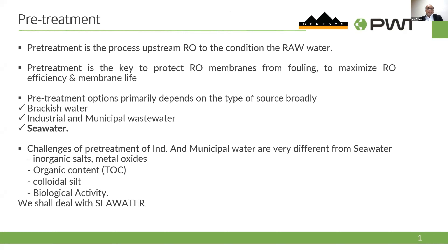Some of the challenges of pretreatment of industrial and municipal water are very different from seawater. If you classify into two categories, industrial and municipal water will require a certain pattern of treatment — sand filter, biological filter, biological treatment, and a DAF. It all depends on what is coming into the raw water: inorganic salts, metal oxide, organic content (TOC), colloidal silt, or biological activity. We shall deal more with seawater today.